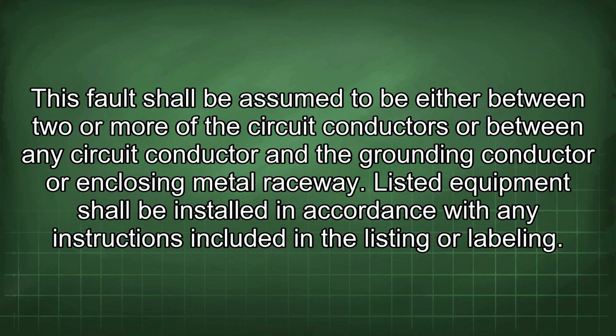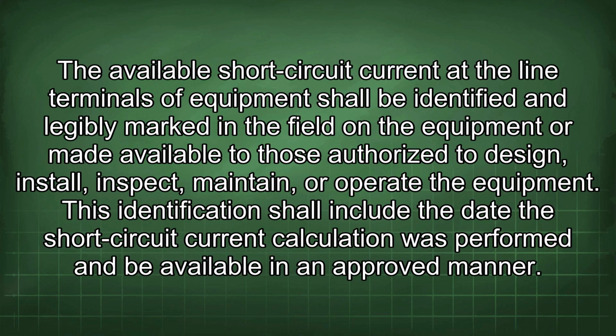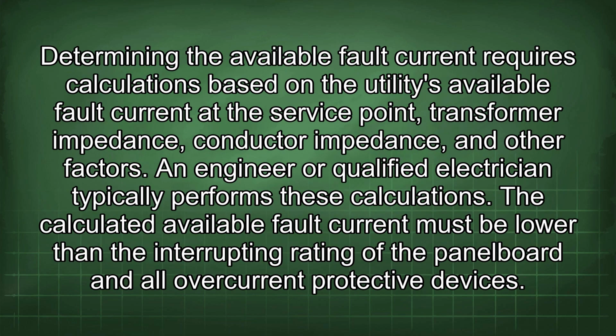Listed equipment shall be installed in accordance with any instructions included in the listing or labeling. The available short-circuit current at the line terminals of equipment shall be identified and legibly marked in the field on the equipment or made available to those authorized to design, install, inspect, maintain, or operate the equipment. This identification shall include the date the short-circuit current calculation was performed and be available in an approved manner. Determining the available fault current requires calculations based on the utility's available fault current at the service point, transformer impedance, conductor impedance, and other factors. An engineer or qualified electrician typically performs these calculations.